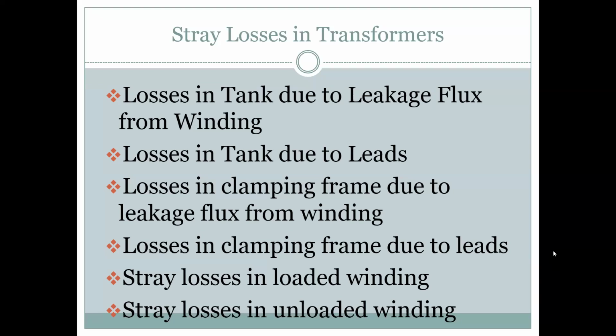Losses in the clamping frame due to leads, and the stray losses in loaded winding. When you load the transformer, there will again be some losses, because the leakage flux will find the shortest path to complete that loop. Then stray losses of unloaded winding. When we keep it in open circuit condition, flux is induced and there are some losses, because the flux will not be able to connect the secondary winding. Normally 6 to 7% of your load loss goes into stray loss. So these are basically wastage, and a lot of concentration goes into how to reduce these losses. The more we reduce this wastage, the more efficiency we get from the transformer.